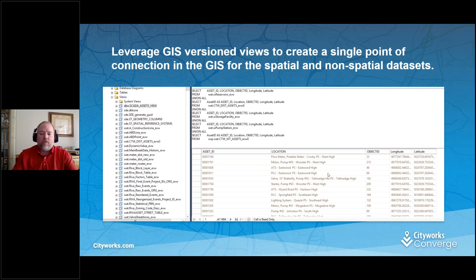The reason we went through this is we also, on the SCADA side, tagged each SCADA tag we wanted to create a work order from with the actual asset ID. So when a SCADA tag is generated for a pump running 1,000 hours, it knows that 1,000 hours ran on this pump and its asset ID is this, so it can tag it into the GIS, which then ties it to Cityworks.